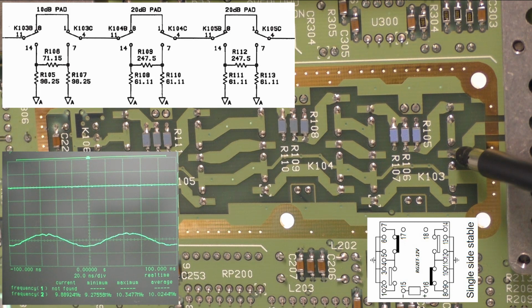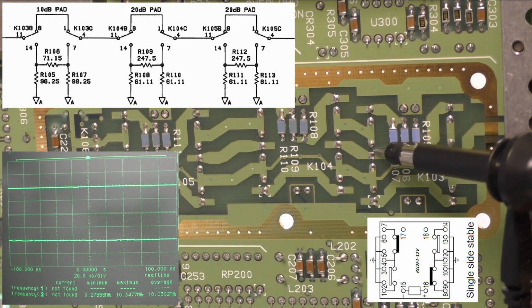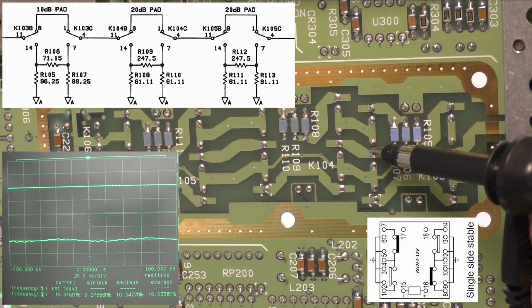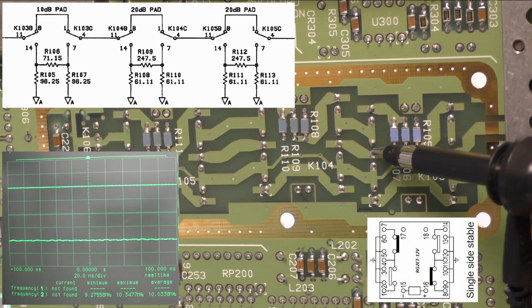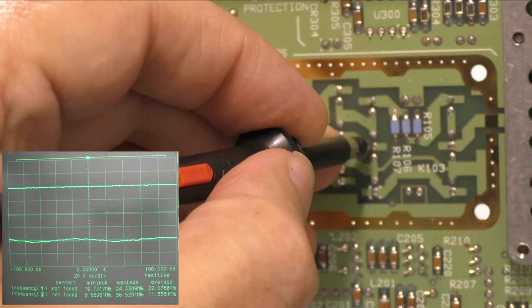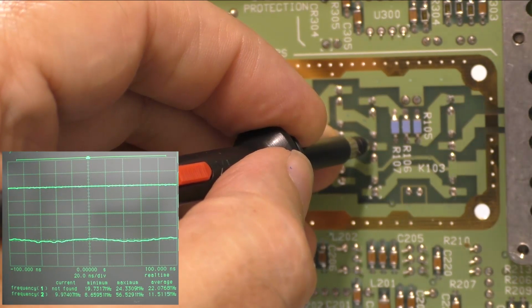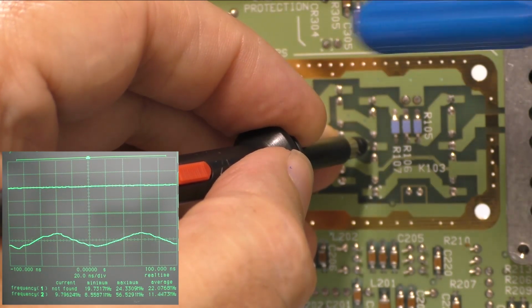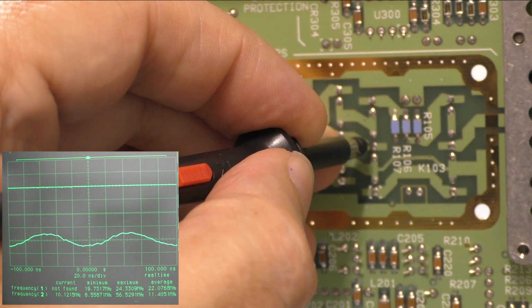We can see the 10 MHz signal. This tells us the input switching relays are probably okay. Place the probe tip onto pin 4 of K103. The signal is not present. This indicates a problem. Whilst holding the probe on pin 4, lightly tap the assembly around K103. We can see the signal is now on pin 4, although we still do not have an output on J3.